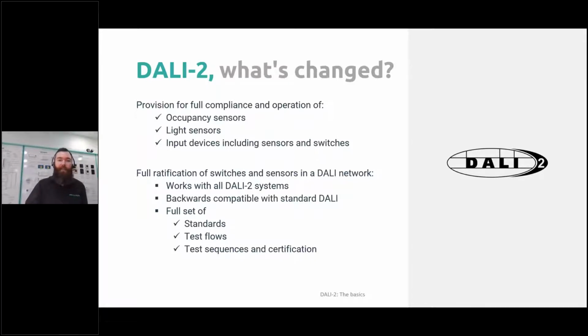The biggest advantage is that it brought in our input devices. In the DALI 1 space, output devices were standardized—things like LED drivers, fluorescent and incandescent drivers, relays, emergency devices, 0 to 10 volt converters—each had subparts describing how those particular devices should work in your system. But input devices, things like PIR sensors, lux sensors, switches, key switches and so on, were not standardized, and it was up to each individual manufacturer to determine how they worked. So the interoperability between those devices was slim to non-existent.